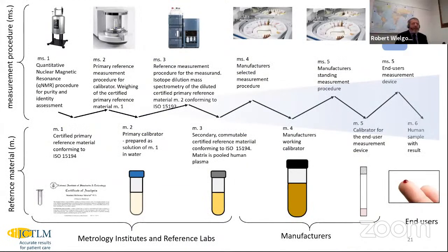This is another picture of the same scheme, but allowing a better visualization of the different types of measurement method and calibrants that are used, starting with the work that's carried out in NMIs, going all the way down to the IVD industry and the patient sample measurement system.